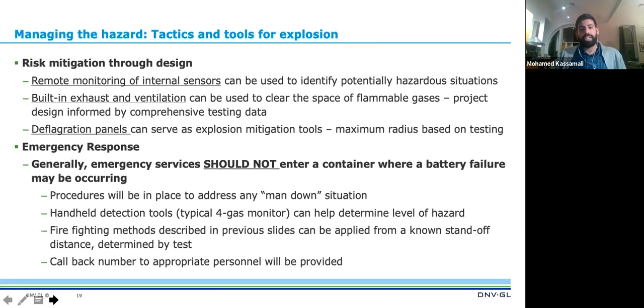There are also deflagration panels, a mitigation and explosion control tool common in other industries, such as oil and gas or hazardous materials buildings. The deflag panel is a design weak point on an enclosure where a certain part of the container's roof flies off more easily than other parts, controlling the direction of the explosion. So almost always you'll see deflag panels on top of the container, to avoid causing debris to fly radially.